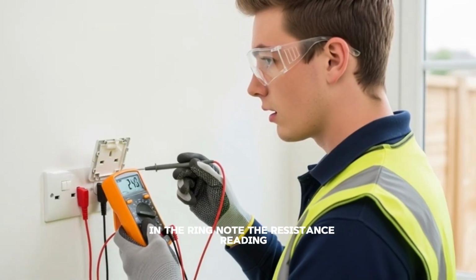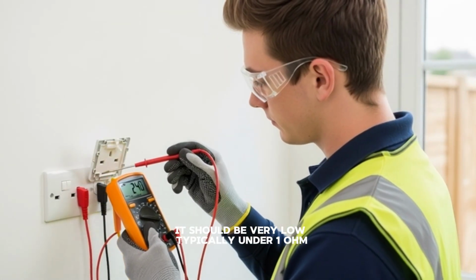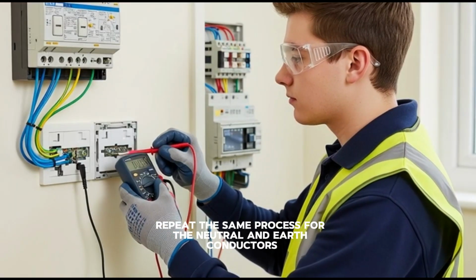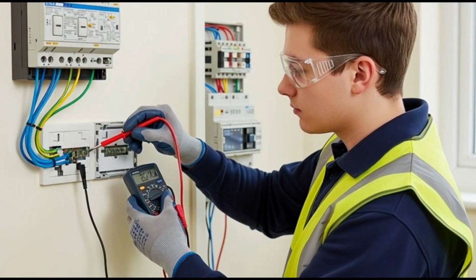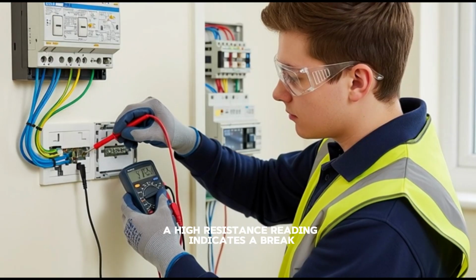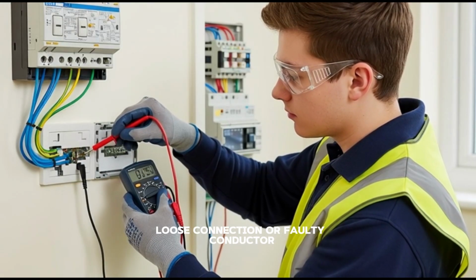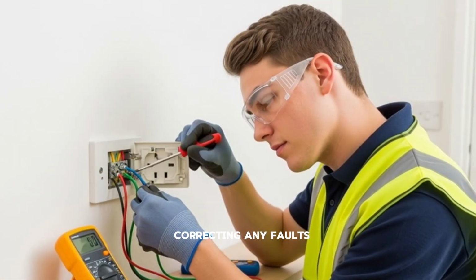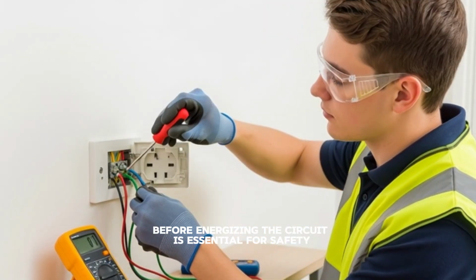Note the resistance reading. It should be very low, typically under 1 ohm. Repeat the same process for the neutral and earth conductors. A high resistance reading indicates a break, loose connection, or faulty conductor. Correcting any faults before energizing the circuit is essential for safety.